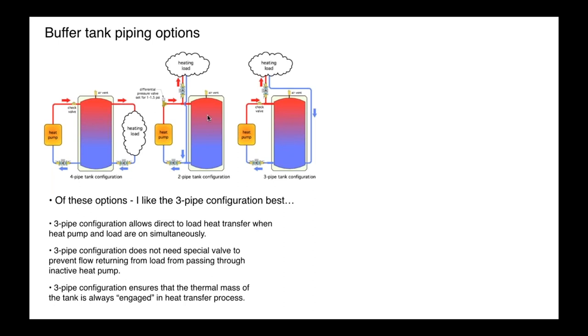This can do similar things. If you're using a two pipe, you need some kind of a way to prevent flow that's coming back from the load. You don't want that flow to go up through the heat pump when it's off. It just dissipates heat into the mechanical room. It doesn't hurt the heat pump per se, but it's an undesirable condition. So we found that putting a differential pressure bypass valve at its lowest setting, about 1 PSI, provides enough forward opening resistance to prevent that. We have not found that the check valve that is in some of the small circulators, those check valves open at about a third to a half of a PSI, depending on what the resistance of this path is right here, including the header and the T's, bottom and top, that might not be enough forward opening resistance.